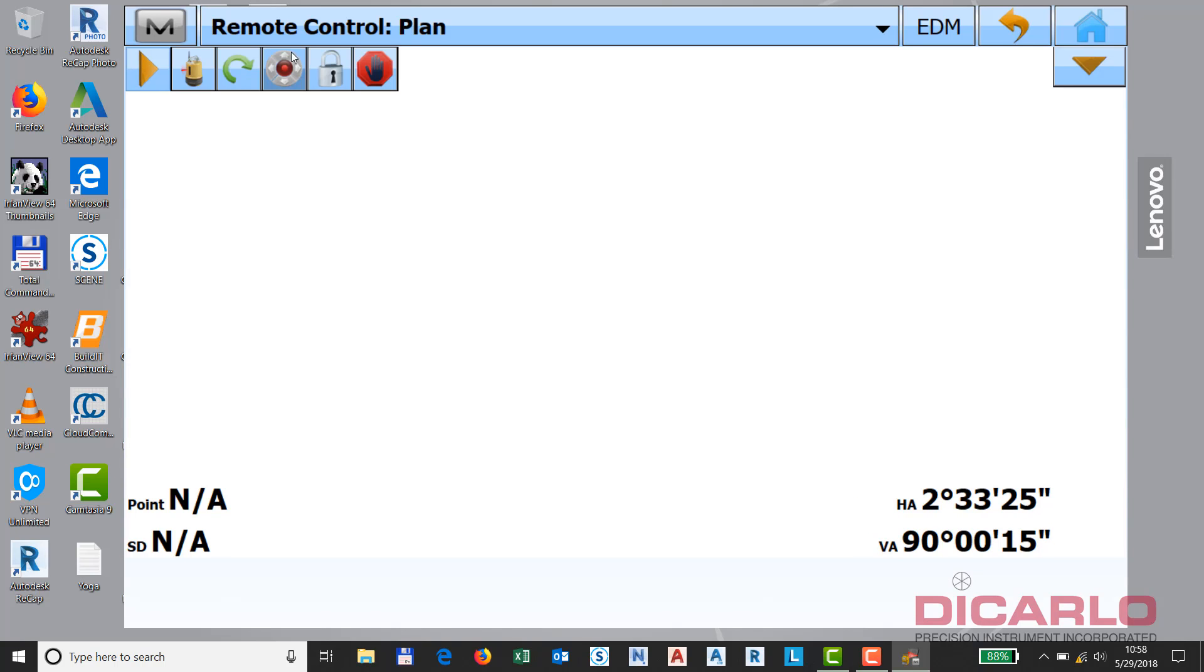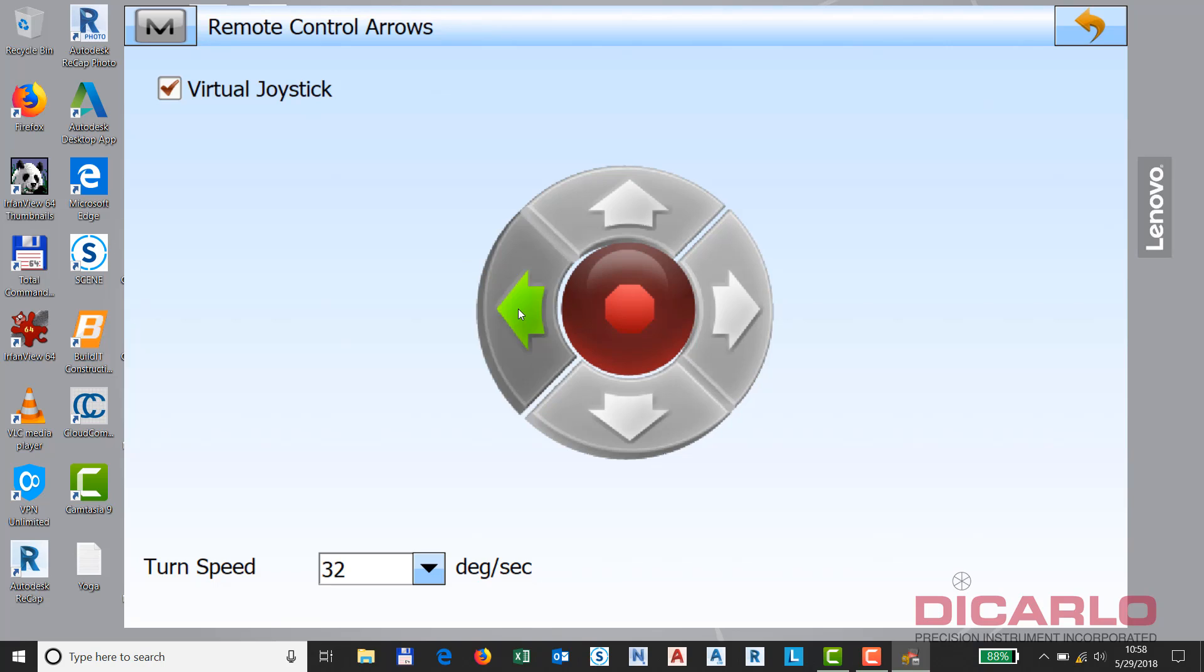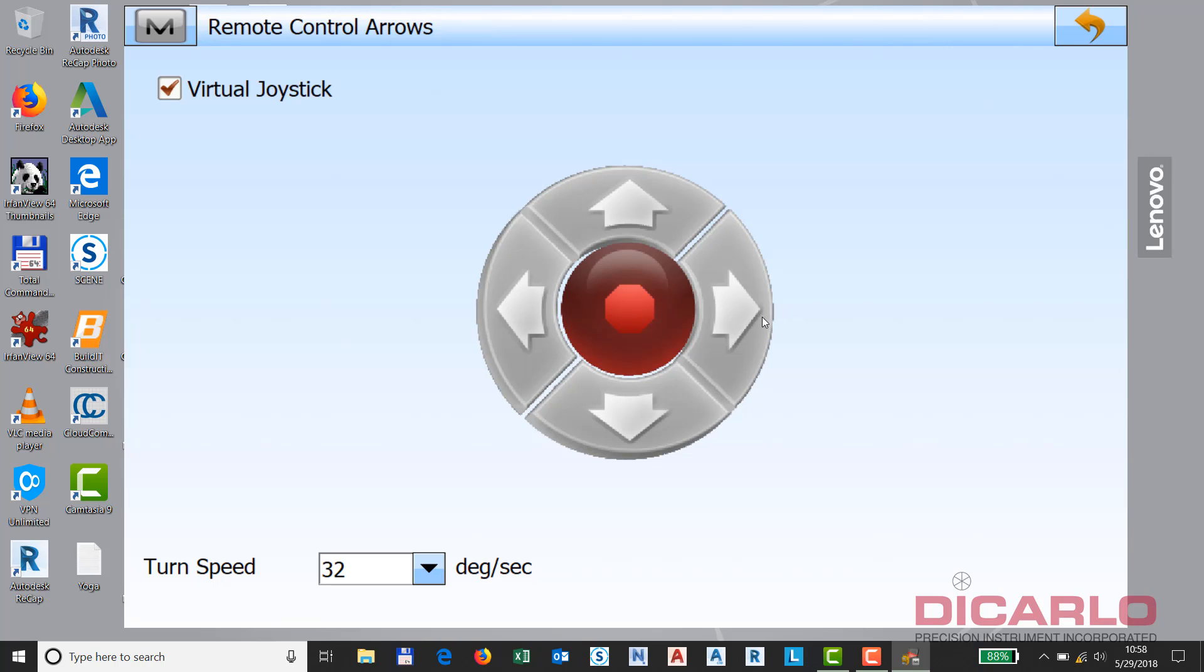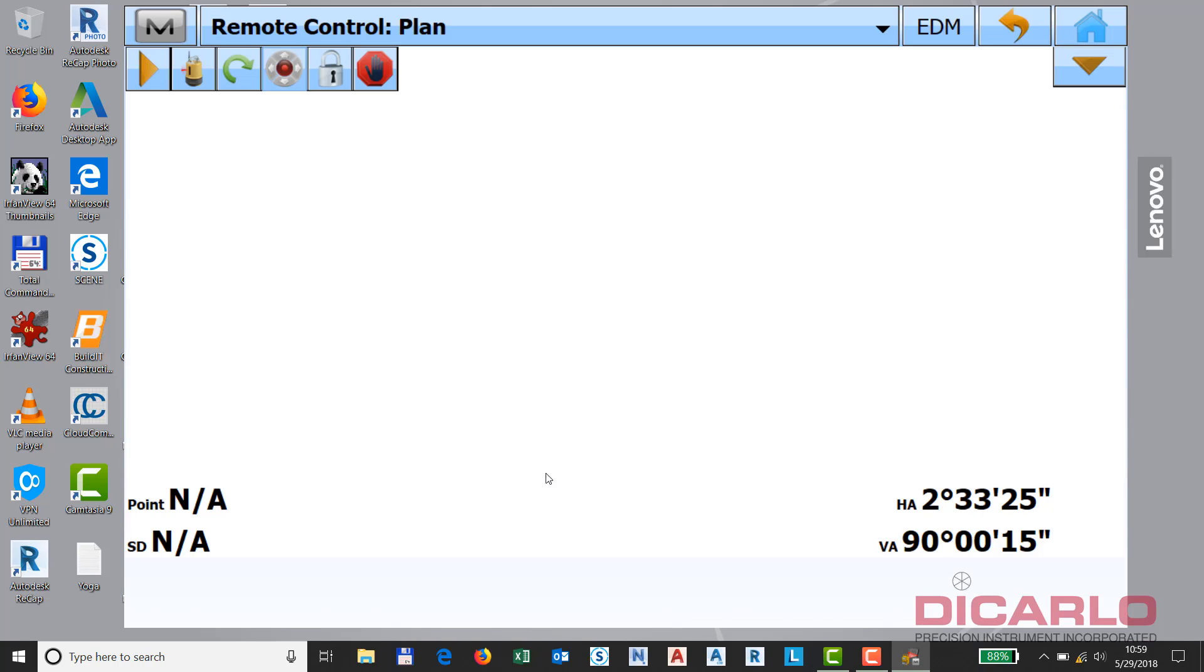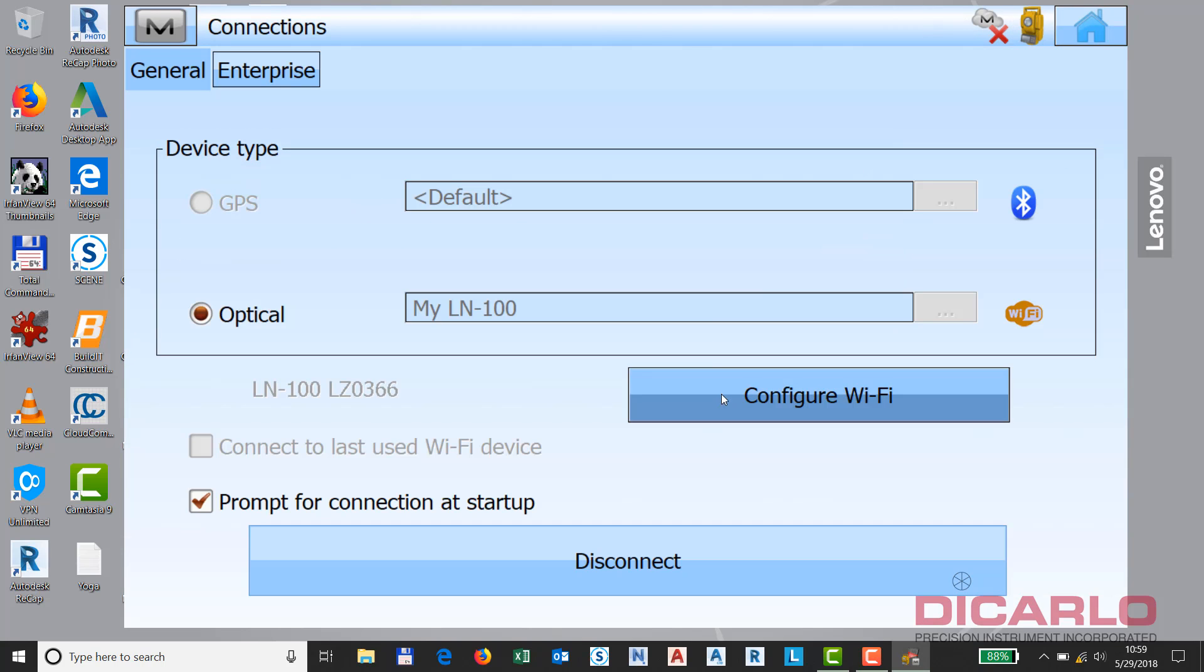It's always nice to just double check that it's actually working by turning the LN100 or just operating it remotely. But without that power off and power on in between, you might find it a little tricky to actually connect to it. Upon next connection, this is not going to be necessary. It's just the very first time you ever connect. You will have to connect in Windows, power off, power back on, let it reconnect automatically, and then magnet field will be ready to connect to the instrument.